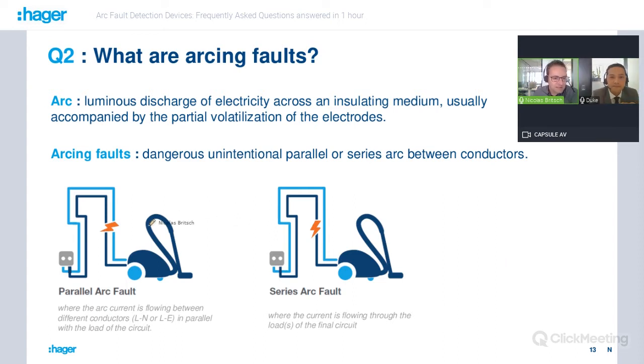So here we make the distinction between two different kinds of fault. The parallel arc fault is a fault between two different conductors. Here it's phase and neutral in this example. And the series arc fault is a fault between two parts of the same conductor. So this is the very basics of arc faults: parallel and series arc faults are the two different kinds of fault that we would like to protect against. It's not only that, but we will see it later.